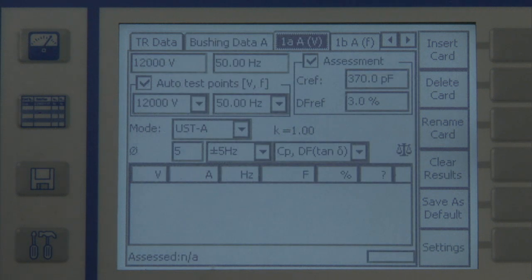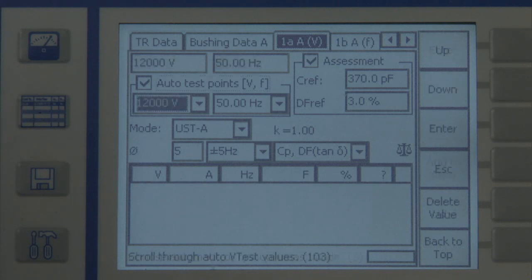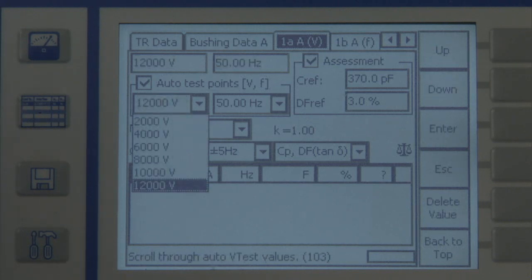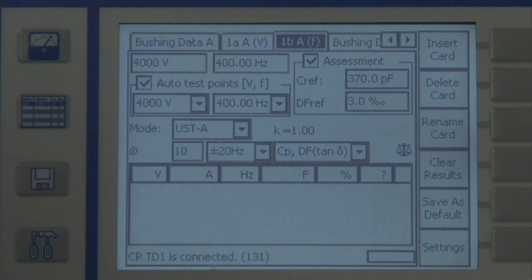The second test card for the bushing of phase A contains the data for the voltage-dependent measurement, in which the dissipation factor or the power factor shall be measured at 2, 4, 6, 8, 10 and 12 kV at power system frequency. The third card includes the previously prepared frequency-dependent measurement.